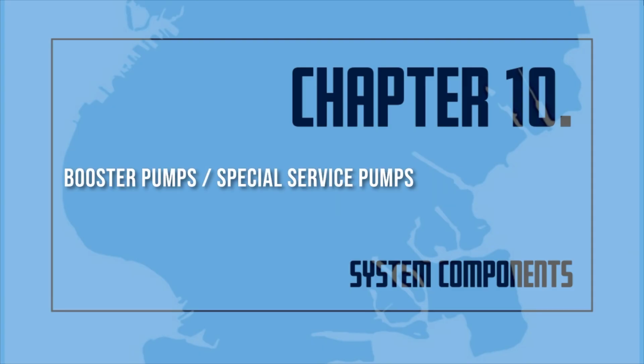Booster pumps, special service pumps. Booster pumps are sometimes used in sprinkler systems. These small pumps with limited power are usually located in the basement or taking suction from gravity tanks. The booster pump is used when the water pressure available at the highest sprinkler head does not quite meet the needs of the sprinkler system. This small pump increases the water pressure in the sprinkler system until it reaches acceptable levels. The booster pump should not be confused with the fire pump or the jockey pump.